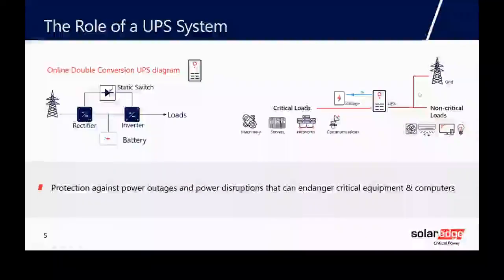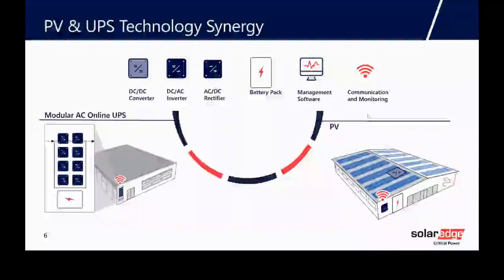This is a very simplified building circuit. Power would come into a building, it would go to a transformer or main LV panel. On that LV panel, you would have non-critical loads directly fed from the mains. You may have a generator, but you would definitely have a UPS feeding the critical loads, normally IT, but can be anything. And obviously the UPS has a battery to keep things going. So that explains the basics of a UPS system.